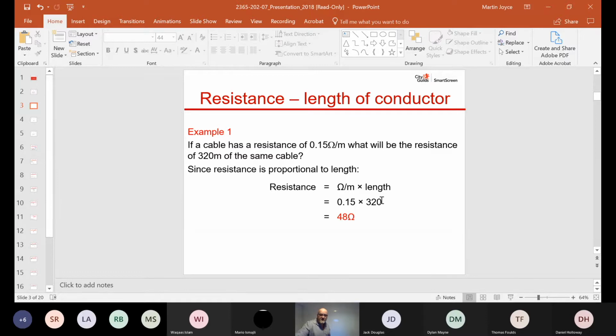In your on-site guide, table I1 gives you the resistance per meter for a size of cable. Where is that table? It's in appendix I of your on-site guide, about page 190 or so. You've got sections 1 to 11, and then the appendices A, B, C and so on, all in the top corner. If you scroll the top corner, you'll see appendix A, B, C, D, up to I. You've got table I1, and it gives you the milliohms per meter.